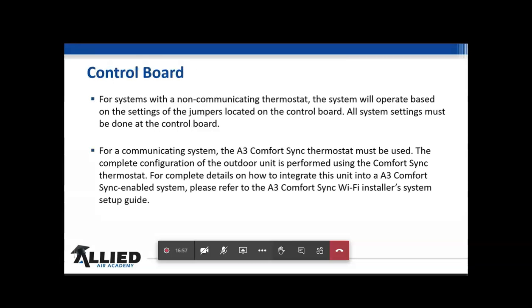All right, so for the control boards for the systems with non-communicating stats, it'll operate with jumpers located on the board. I'm going to go over the jumpers in just a few moments. For the A3 communication, we're going to do it on the thermostat, and I've got some screenshots coming up here to show you why it's important to look at this. So just remember, if the contractor does decide not to use an A3, they can do that. That is definitely their preference, but they're losing a lot of troubleshooting ability when they do that.